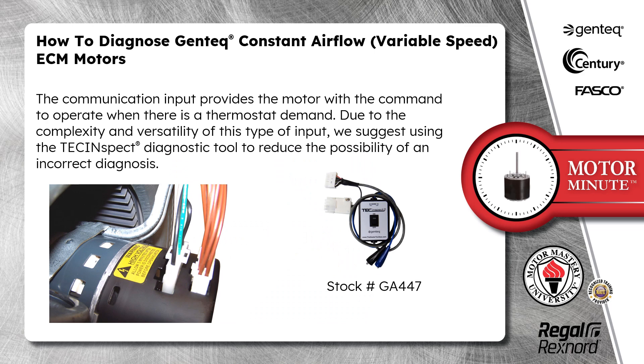The communication input provides the motor with the command to operate when there is a thermostat demand. Due to the complexity and versatility of this type of input, we suggest using the TECInspect diagnostic tool, stock number GA447, to reduce the possibility of an incorrect diagnosis.